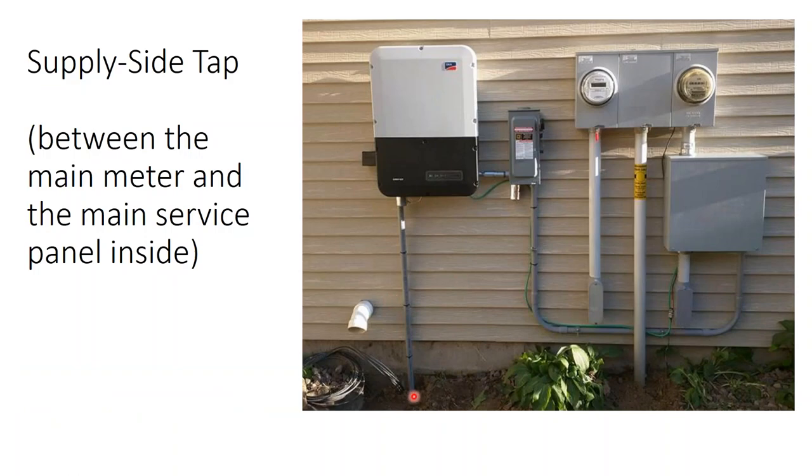So back to the half moon array, the ground conductors are coming up here. Here's our extra for expansion down the road. We just put them in a box and buried them. Going up into the inverter, secure power supply, coming into the AC disconnect. Here's our lightning arrestor that protects against surges on the AC side. Then we go into our line side tap that's inside this box. We have our utility bottom fed service entrance conductors.